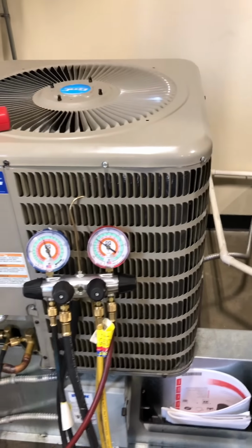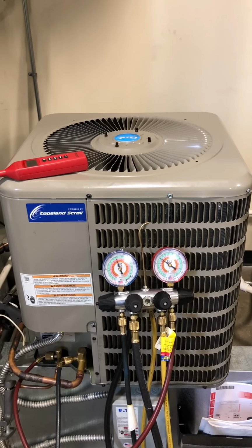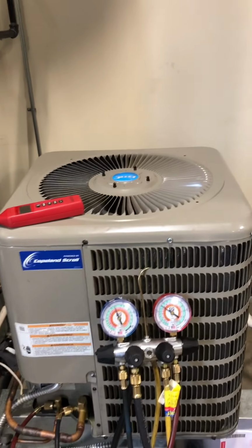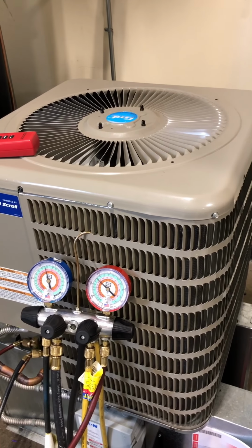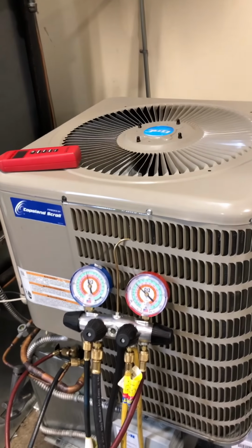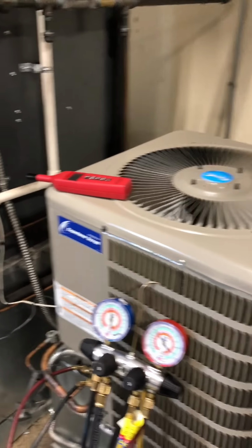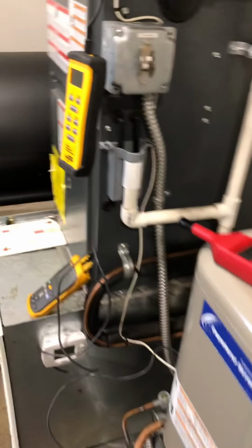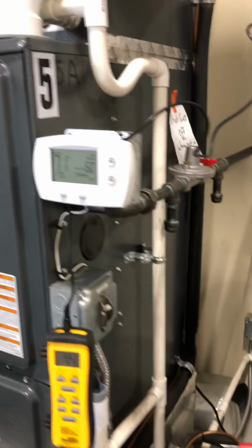Other thing I'm going to check, and a lot of guys forget about this one, is my condensing split. What the hell does that mean? Well, condensing split is the difference between the outside ambient temperature, so the air that the condenser is using to cool the refrigerant down. Right now I know we're in a training environment, we're condensing with inside air, but we're going to use that for an example, okay? So my ambient temperature is that bottom number, 70 degrees. 70, 71, just like what the thermostat says, it's the same air.